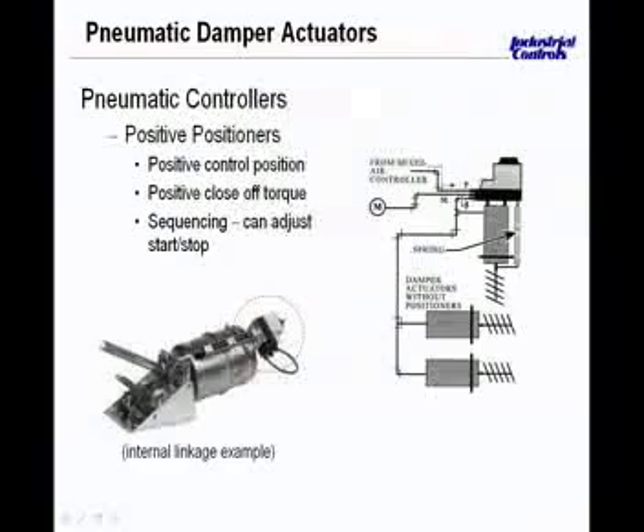I'm going to send that out on the branch line to these two actuators, or three actuators rather, and be able to actually take the 20 pounds of air and move this stem against the airflow that's going against us, is not allowing this damper to be at 50%. So once this is at 50% and the controller says I should be at 50%, there's no more movement, and this positive positioner then is helping do its job with the damper actuator. Right, and so not only can we sequence, but we gain additional thrust by use of a positioner. And really, when you see a lot of stiction, you definitely see it in dampers.